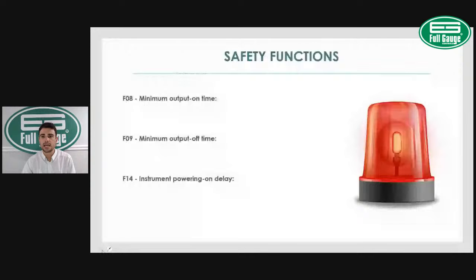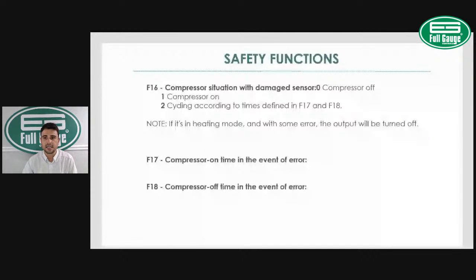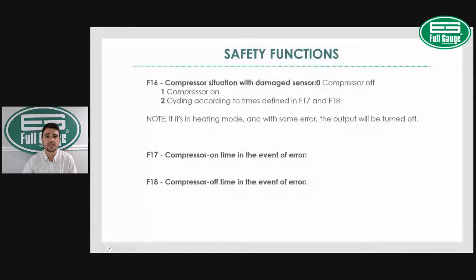And the last function we're going to look at today is F16, which is the compressor situation with a damaged sensor. So let's say, for instance, your sensor fails, you have the option of the unit continuing to work. You can actually set the compressor to keep running. If you set F16 to 1, the compressor will run continuously in case of sensor failure. Or if you set it to 2, the compressor will cycle between time on and time off. And those times are set on the F17 and F18 parameters.